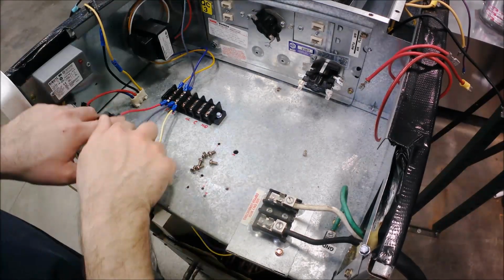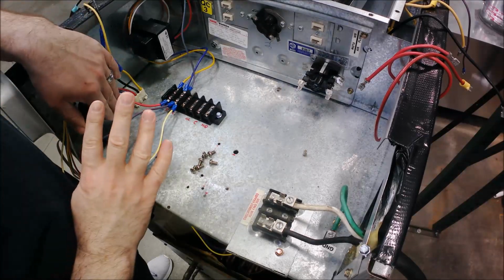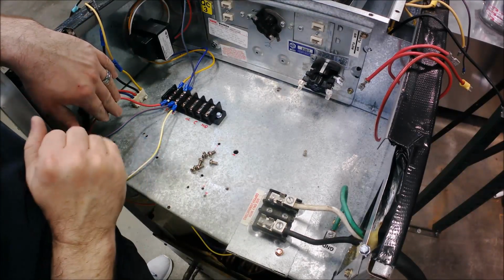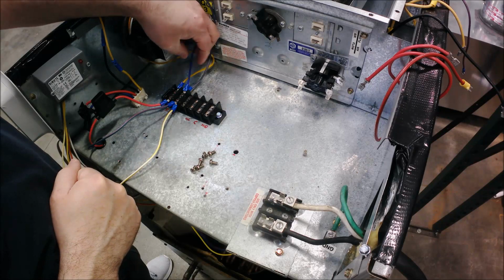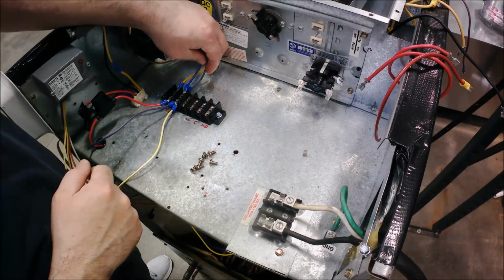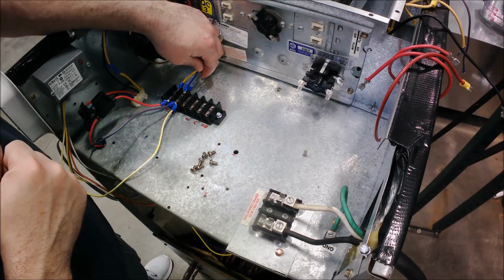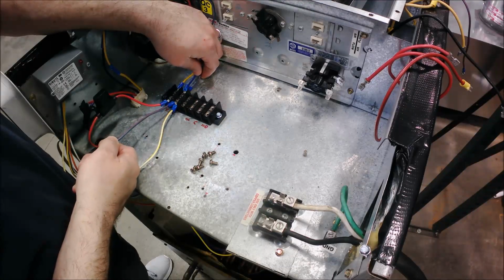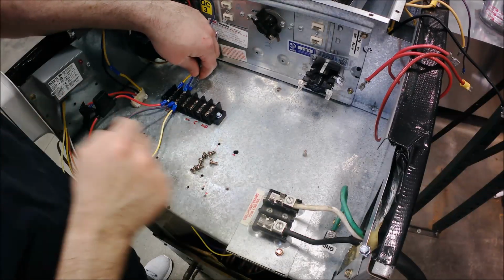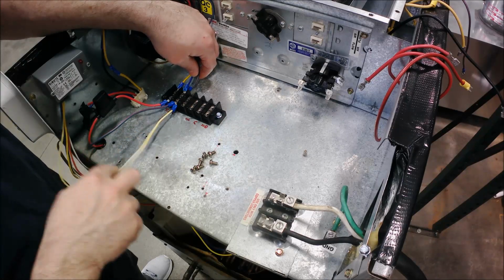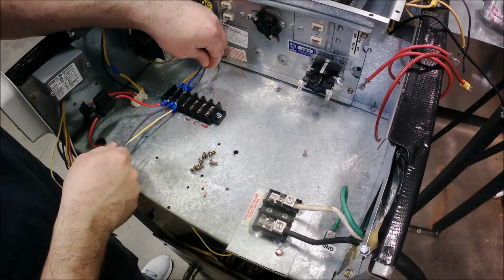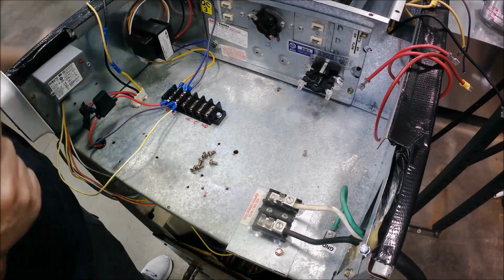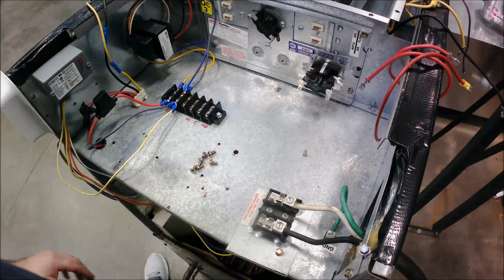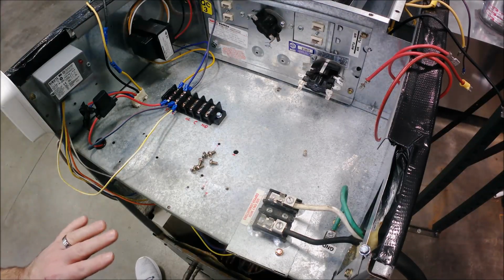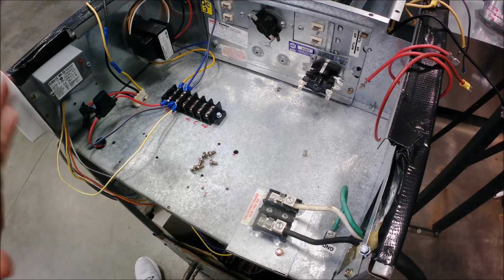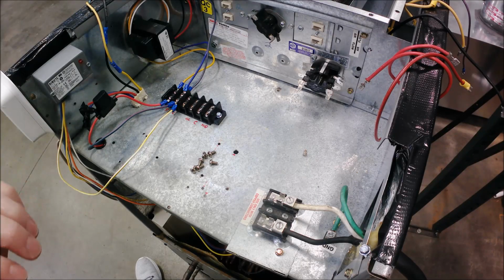All right, so here are 4 low voltage connections on the common side. I've got the original common from the transformer. I'm going to have my common to the sequencer that we're going to wire in just a second. I've got my common from the thermostat connection, the thermostat itself, and I've also got my common from the relay. So there's 4 of them. They're all coming back and ultimately going to go to the transformer. So now we're going to drop down here and start to wire the thermostat connections.